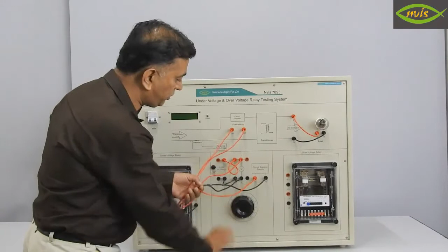Before switching on, keep in mind that your variac position should be in the zero voltage position, that is the fully anti-clockwise position, and the MCB is switched off at this moment. So I am going to switch off the MCB. Here you can see the under voltage relay status is tripped because no voltage is fed. So it is understood that it is tripped right now. Physically also you can see from here that it is tripped. This white terminal, when it is in contact with this rod, means this relay is tripped.